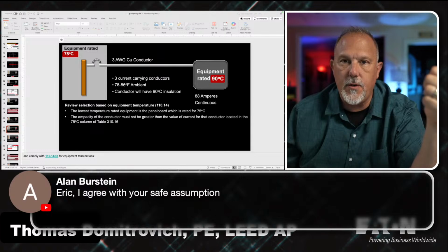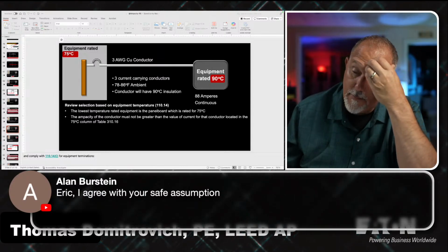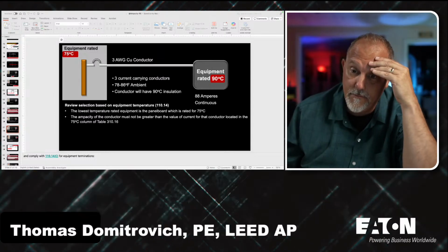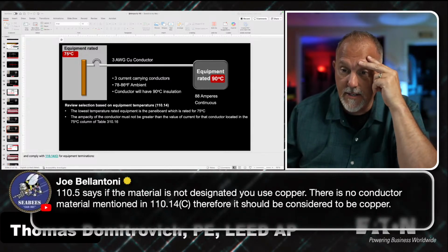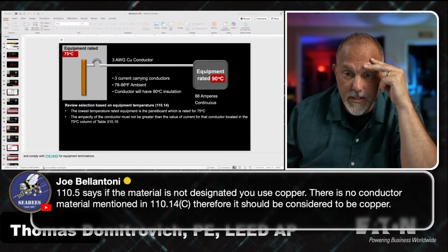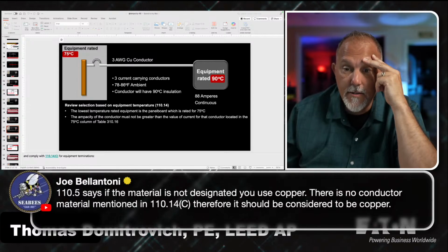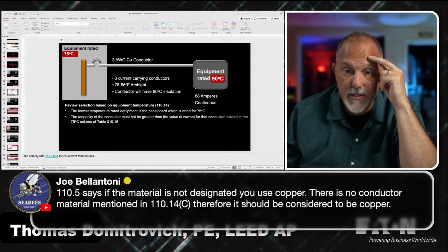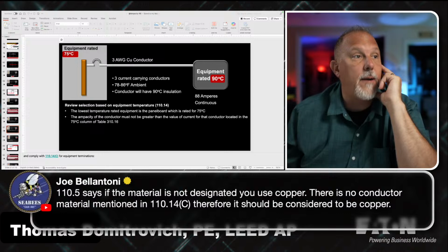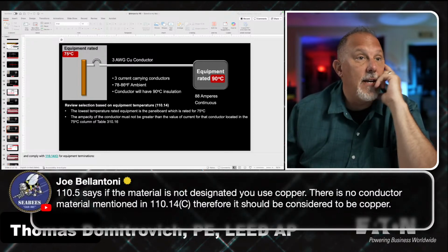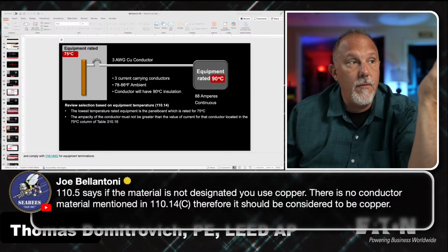You'll upsize your equipment. You know what I might do? I might do this based on 60. We're going to do this based on 60 if I got time. 110.5 says if the material is not designated you use copper. There is no conductor material mentioned in 110.14(C), therefore it should be considered to be copper.